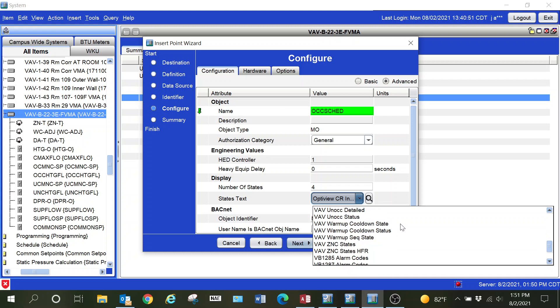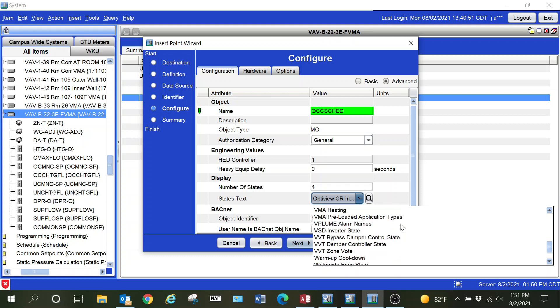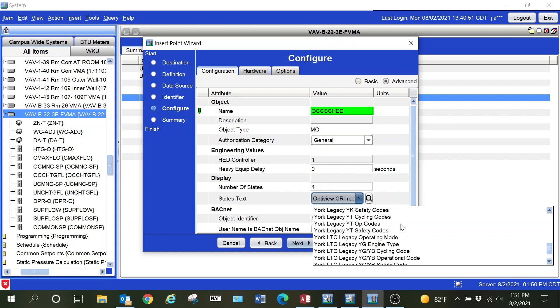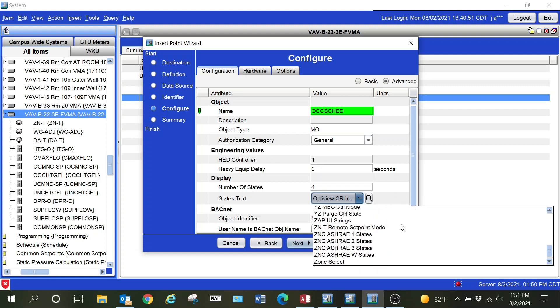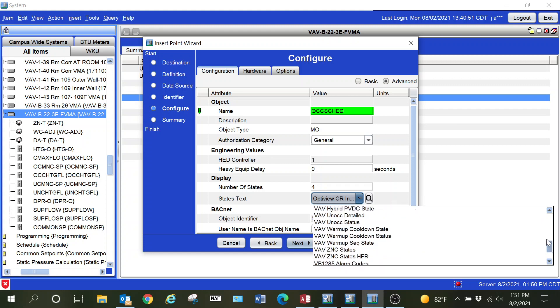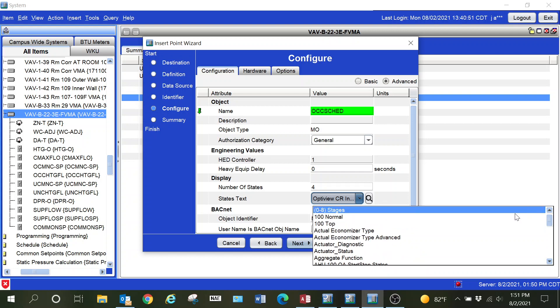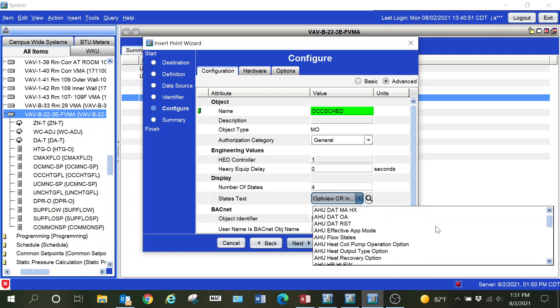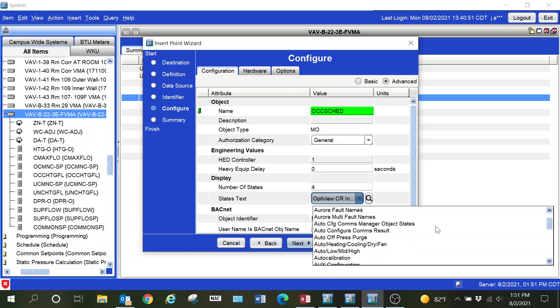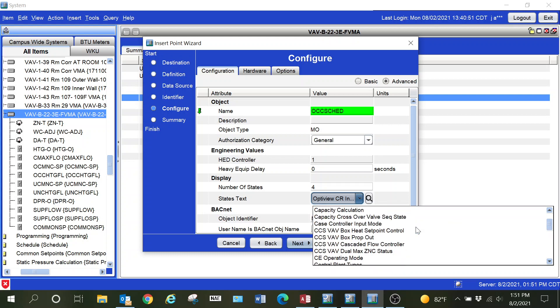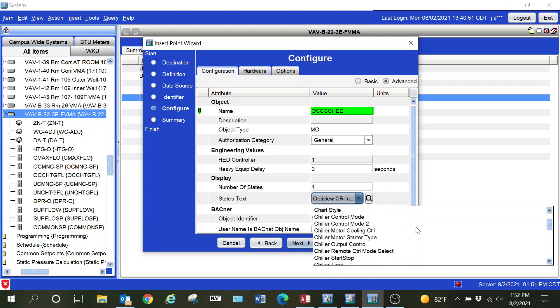If they get pulled in incorrectly using the PRN file, you can go in and correct them. This was a VMA 1420 that had failed. We replaced this device with a VMA 1630 and simply changed the communication on the 1630 from BACnet to N2.